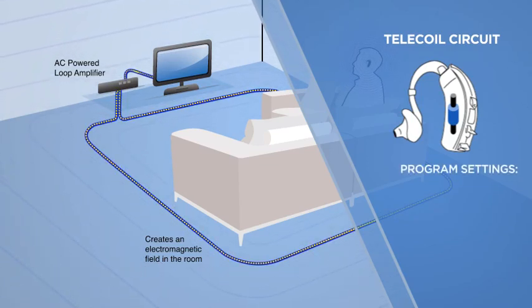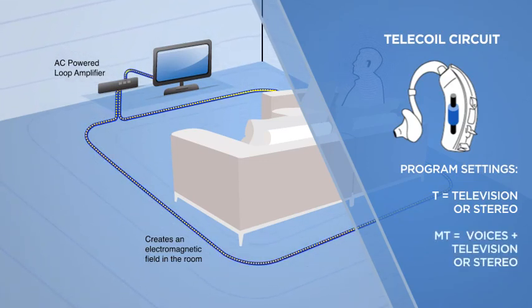Many hearing aids and implants can be programmed to allow for two settings: Telecoil or T and microphone plus telecoil or MT. Having these options allows you to choose to hear only the television or stereo (T) or the television or stereo system as well as conversations by your family, friends and colleagues in the room (MT).